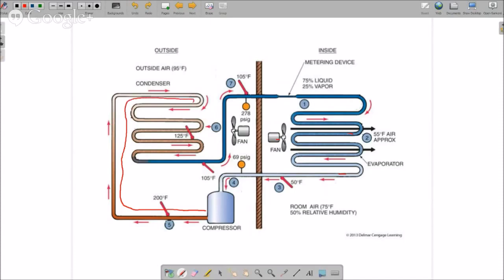The refrigerant goes through the condenser just like it should, but instead of beginning to back up at the normal point, it backs up earlier on in the condensing unit. This area is now all liquid where it should still be changing state. It backs up and spends a longer time in the condenser, taking longer to find its way up to the metering device.